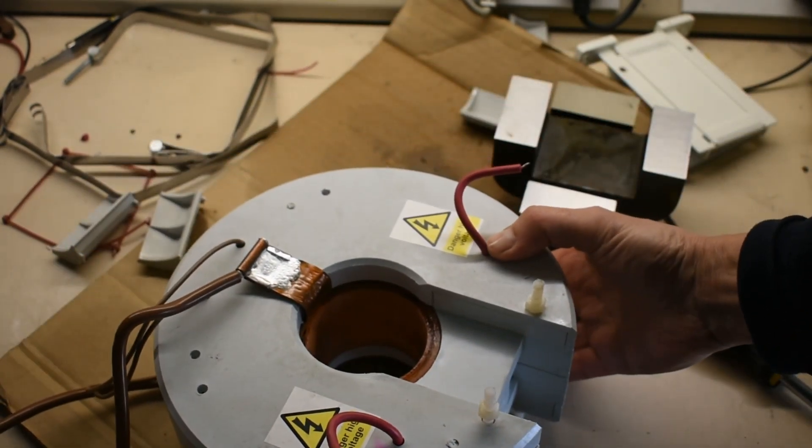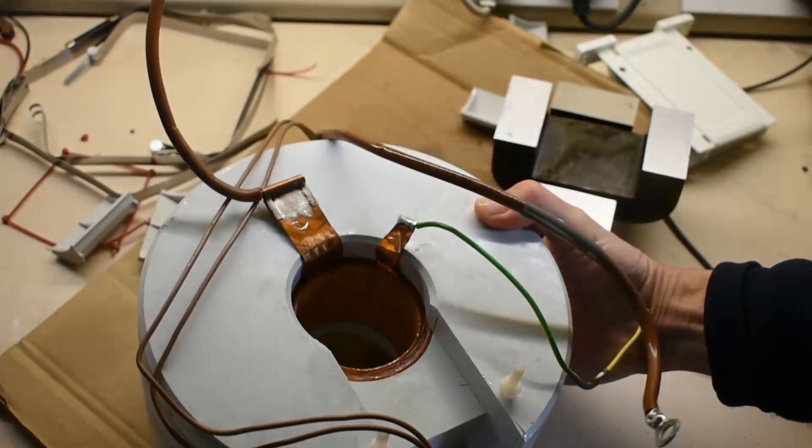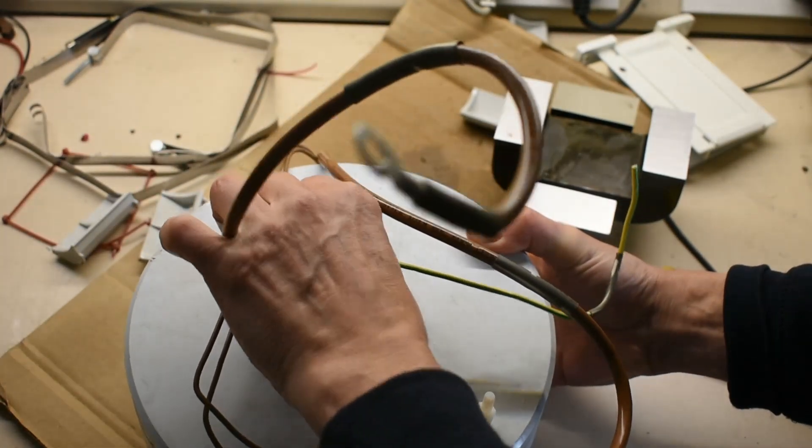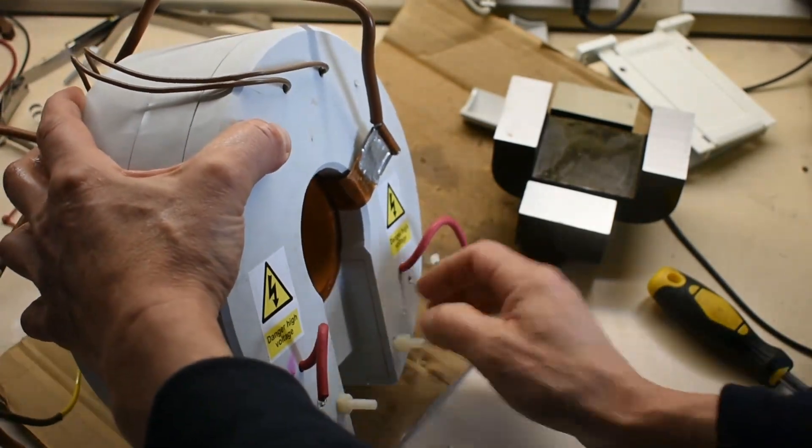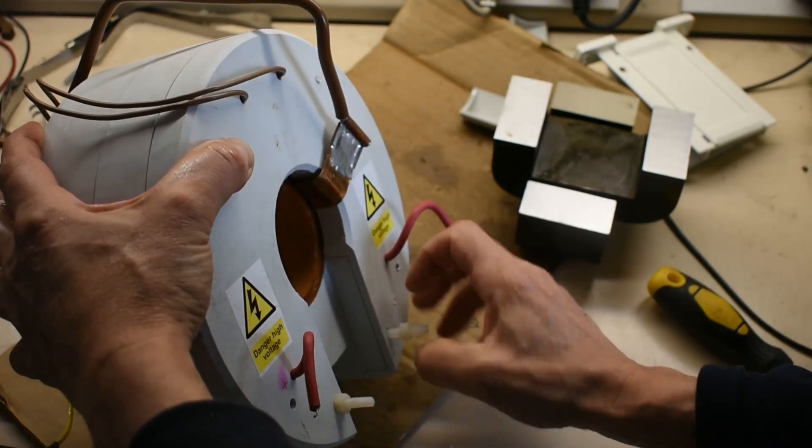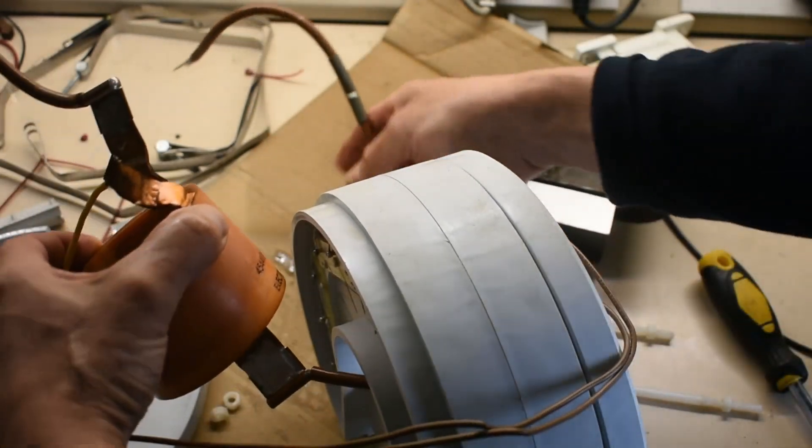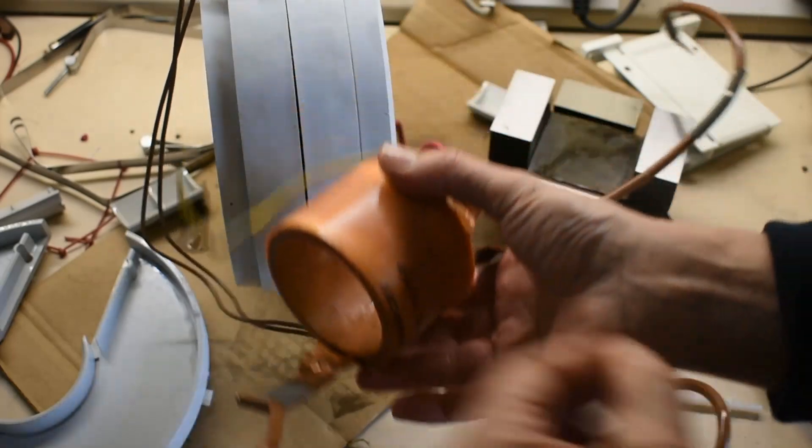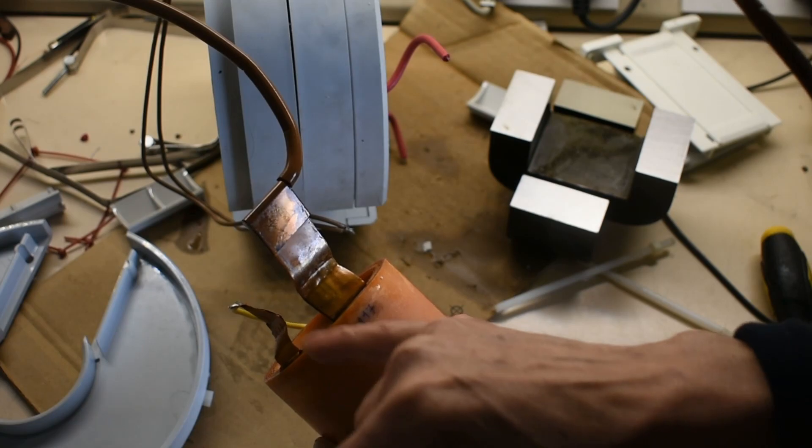And then that lets us see into where the primary windings are. So the primary winding is also screened with an earth. So this can then be removed once the covers come off. So the covers are clamped with a nylon screwed rod and allows the covers to come off. And the primary coil then can be extracted. The primary coil here, the manufacturing date is 93. And you can just see that that's the screening on both inner and outer side of the primary.